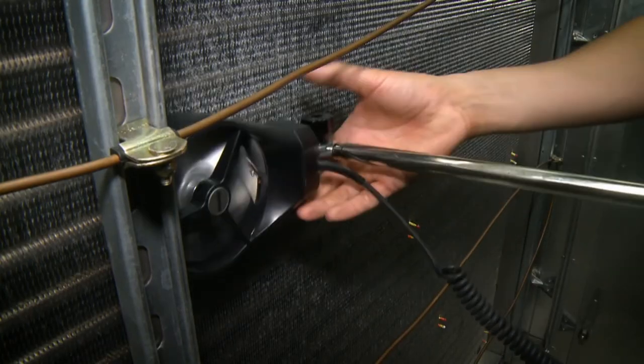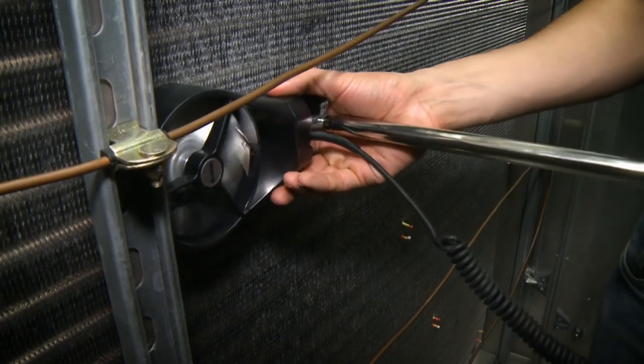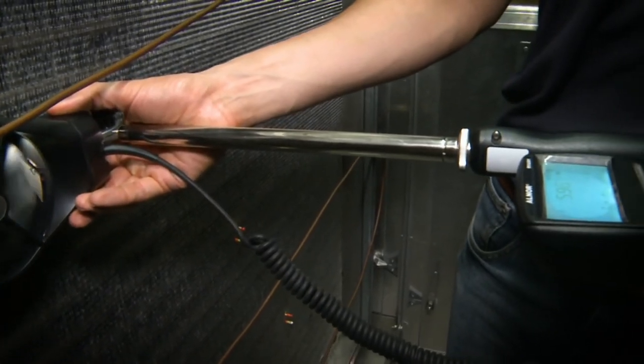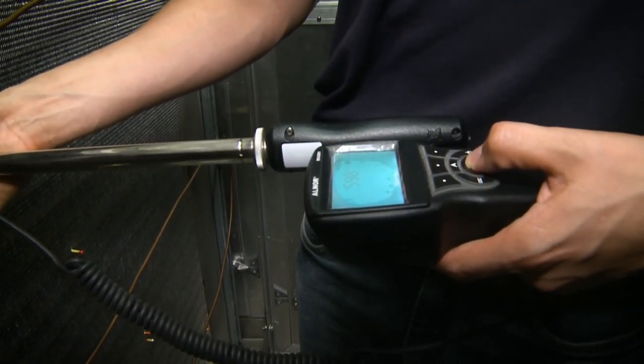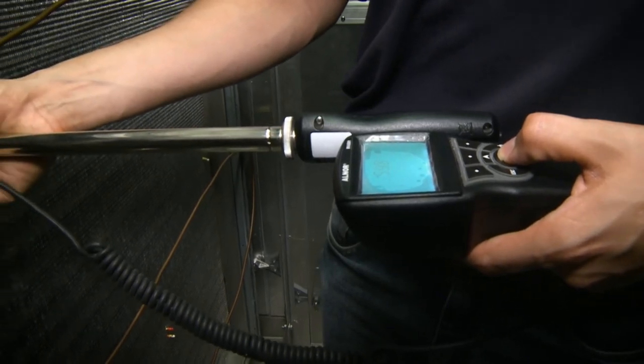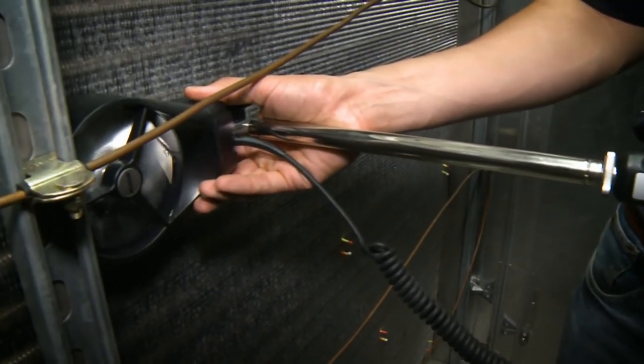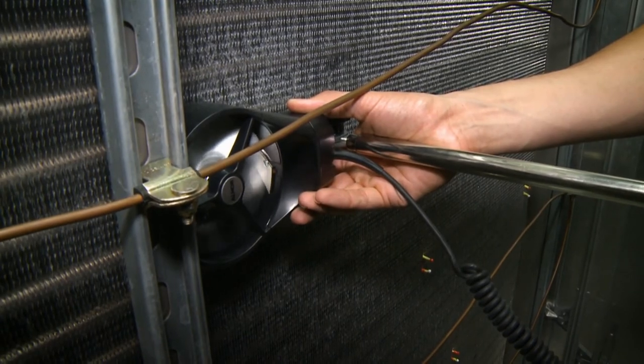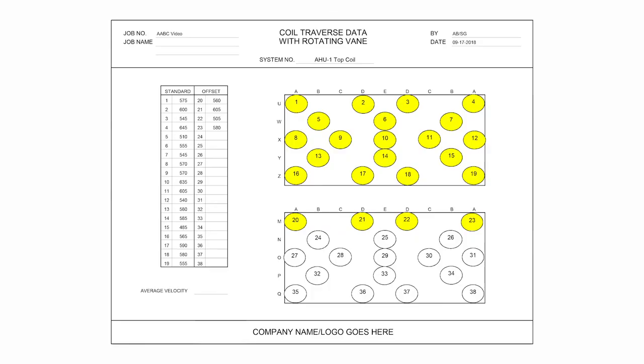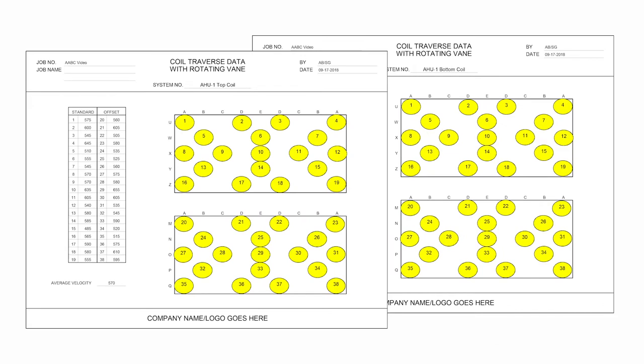Since the center position points for standard velocity reading location 6 and offset velocity reading location 25 are obstructed by the coil frame, the vane anemometer's head was positioned to the closest area possible for the velocity readings. For the remaining position points, continue to follow this procedure until velocity readings are complete for 38 position points on each coil.